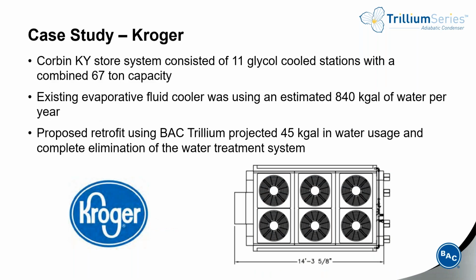Last, let's look at an example for a Kroger store in Kentucky. The system consisted of 11 glycol-cooled stations with a combined capacity of 67 tons. Their existing evaporative fluid cooler was using an estimated 840,000 gallons of water per year. They looked at a 6-fan Trillium adiabatic fluid cooler that would project to use only 45,000 gallons of water and would allow them to eliminate their water treatment system.